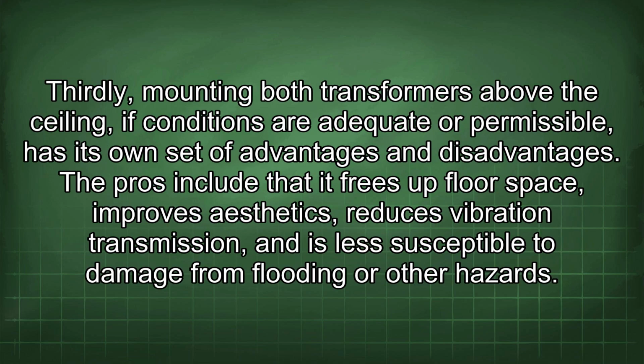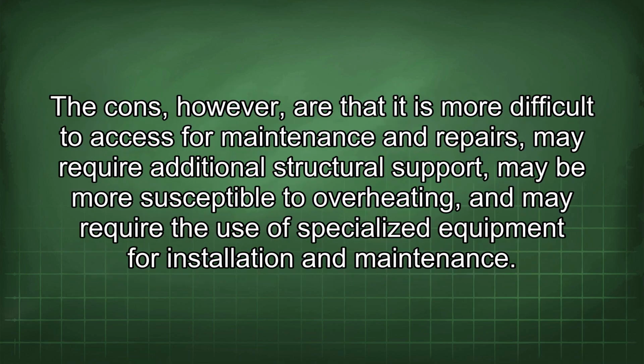Thirdly, mounting both transformers above the ceiling, if conditions are adequate or permissible, has its own set of advantages and disadvantages. The pros include that it frees up floor space, improves aesthetics, reduces vibration transmission, and is less susceptible to damage from flooding or other hazards. The cons, however, are that it is more difficult to access for maintenance and repairs, may require additional structural support, may be more susceptible to overheating, and may require the use of specialized equipment for installation and maintenance.